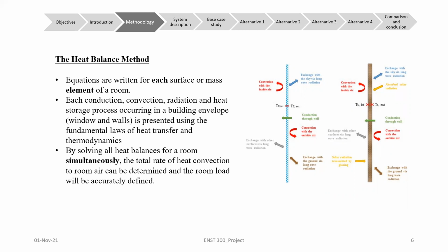The method accounts for the long-wave radiation heat exchange between the sky and the outer face of the wall, as well as the radiation heat exchange with the ground. In addition, a short-wave heat exchange takes place between the wall and the sun rays. In addition, convection takes place due to the speed of the air which is in contact with the outer face of the wall. At last, the heat is also conducted through the wall material by conduction. The same heat exchange processes take place for the glass, except for the short-wave heat exchange, since the window is reflecting the light and the percentage absorbed is neglected.